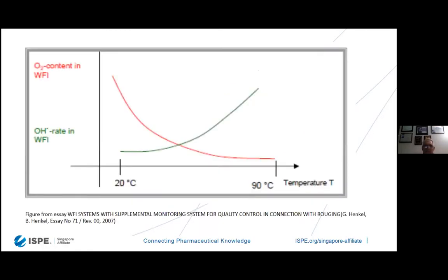This particular screen shows what happens with temperature. When we increase in temperature from 20 degrees to 90 degrees C, what happens is that the amount of hydroxyls that are produced in WFI water increase almost exponentially. And the oxygen content is actually degasified. And the oxygen content goes lower as the temperature gets higher. The higher the hydroxyl radicals, the more corrosion that can ensue. That's why corrosion happens at very high temperatures in a very rapid manner.